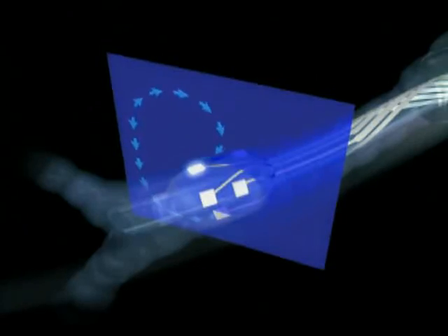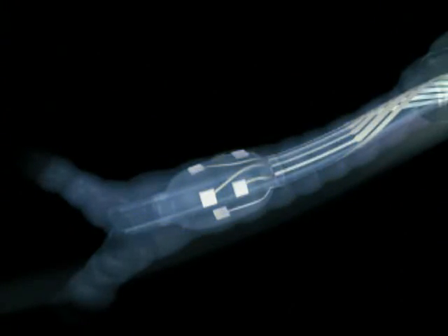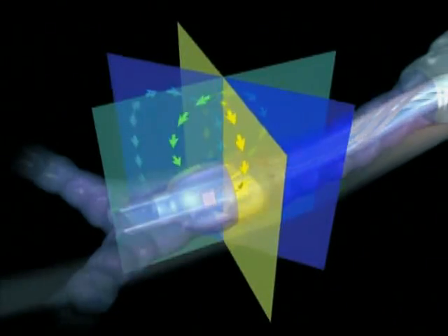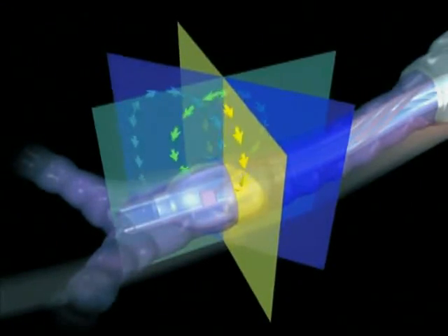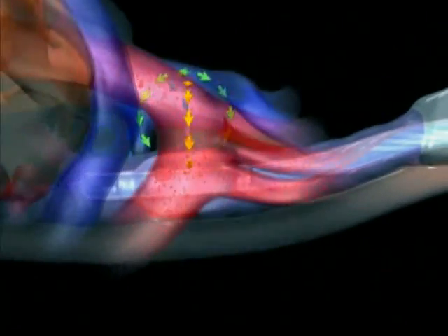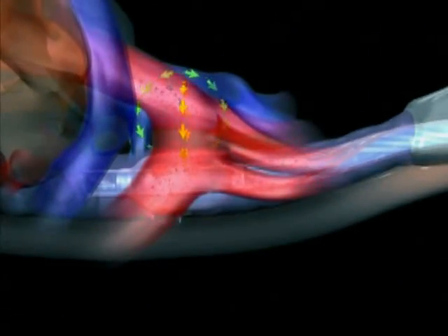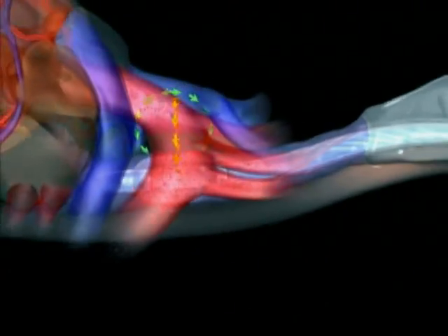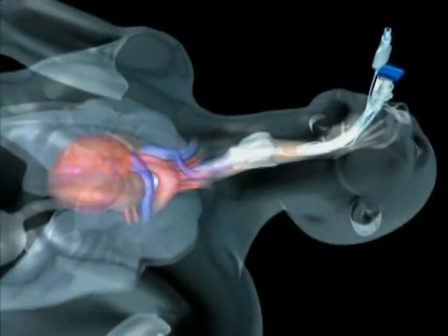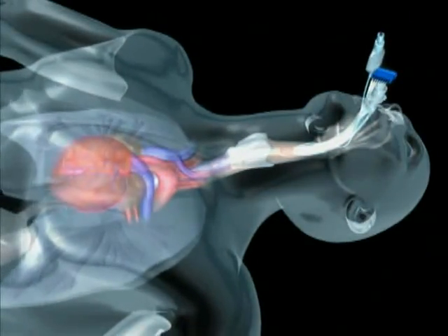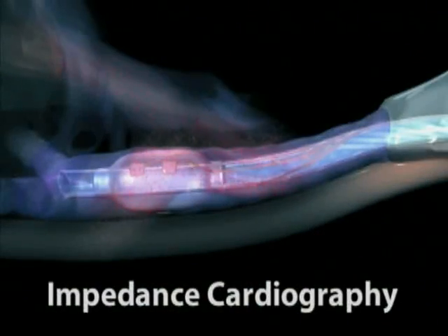A total of 12 combinations of electrodes can be used for the impedance measurement of flow. If a signal is weak or lost on one channel, the ECOM algorithm can search and select another electrode combination. The result is that the ECOM endotracheal tube does not have to be adjusted once it's positioned in order to obtain usable signals. Impedance cardiography uses the principle of blood conductivity to measure cardiac output.